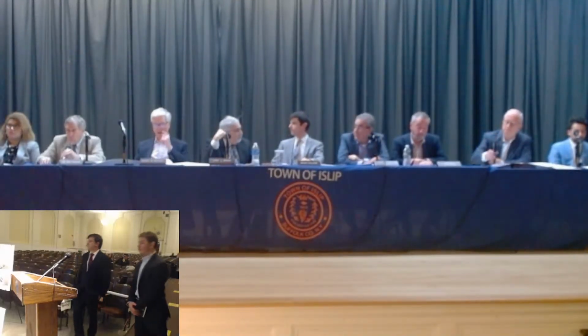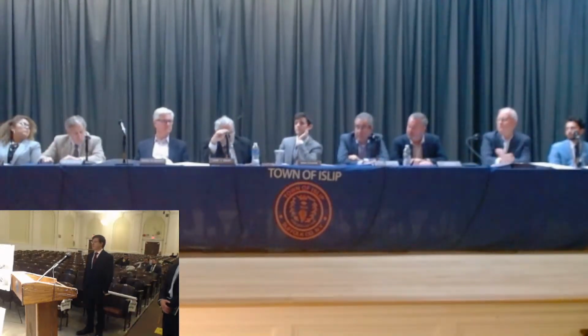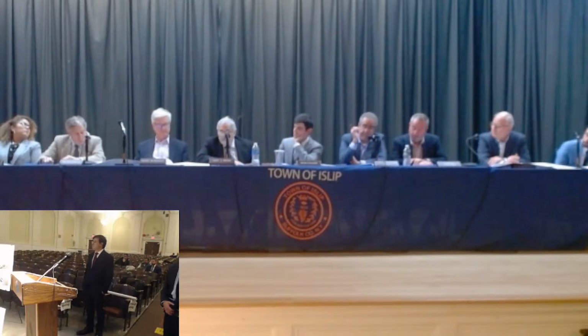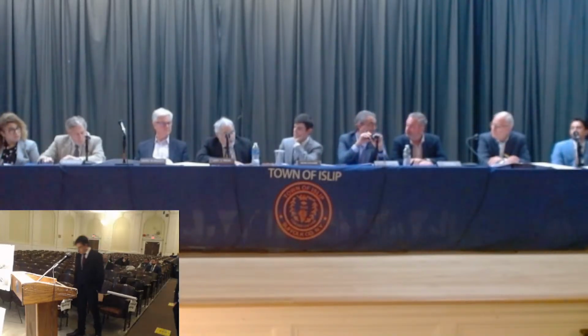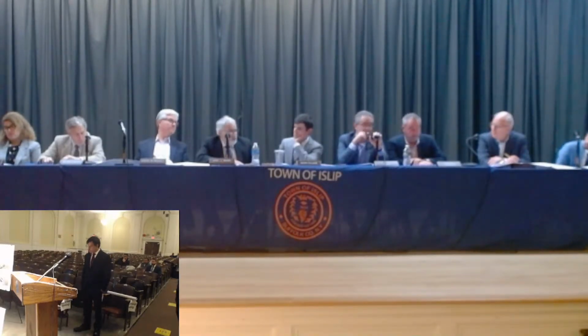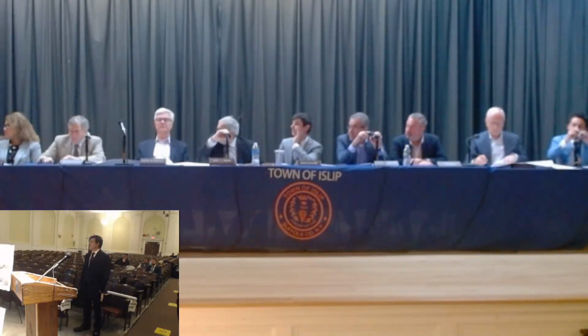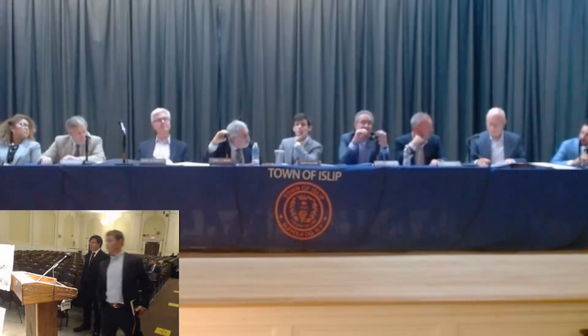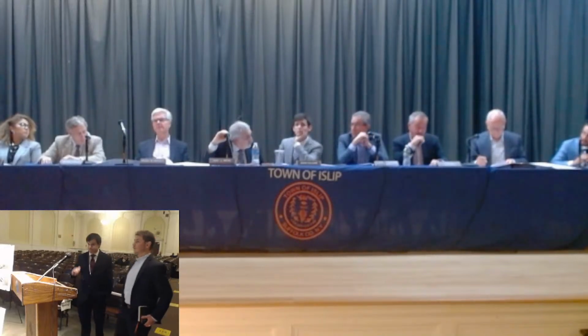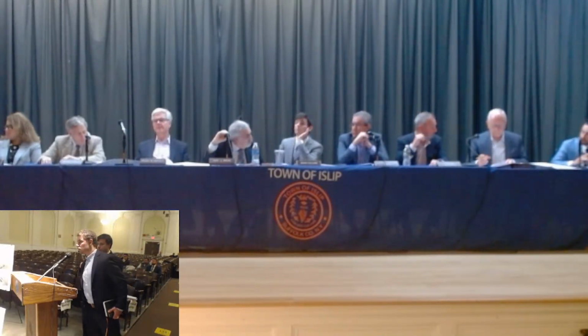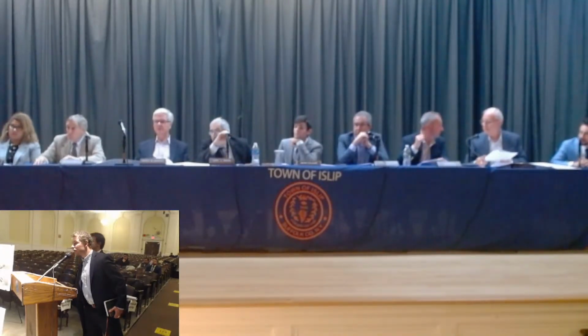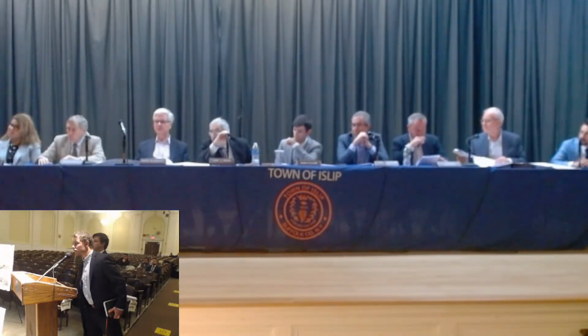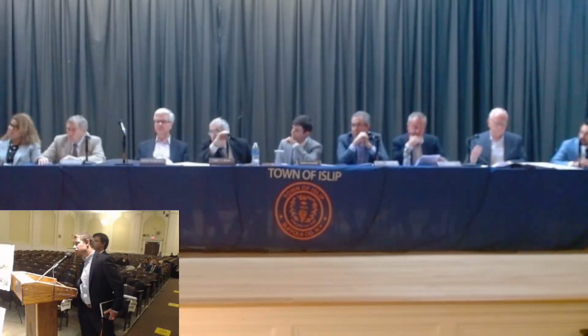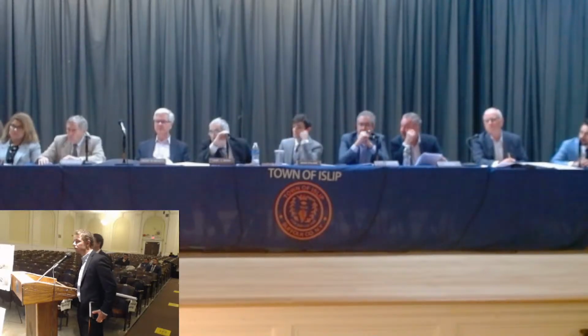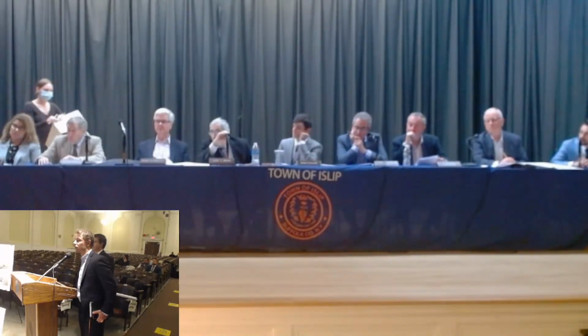Okay, thank you. Mr. Bruno. Yeah, this one might be for Mr. Gonzalez. During her report, Kelly had mentioned that the lighting masts are about 55 feet tall. Does our lighting code permit that? To my knowledge, the maximum height of any light poles in the town is 20 feet to the bottom of the fixture per the zoning code. If I may clarify, those were proposed lightning masts within the project substation. There will be 3 of them total at a height of 55 feet. And this is in order to comply with IEEE standards, which require certain grounding for high voltage equipment. So that's the purpose of the lightning masts.